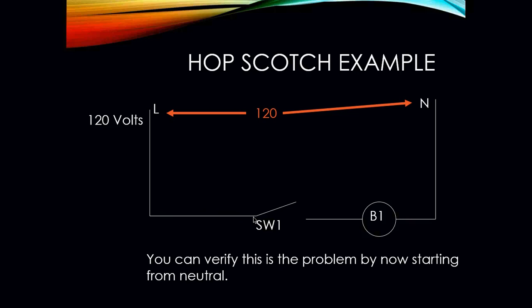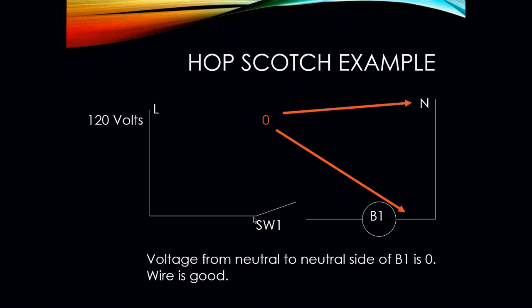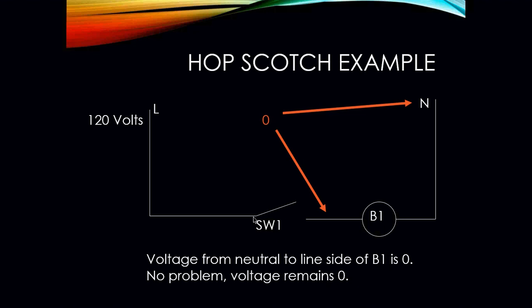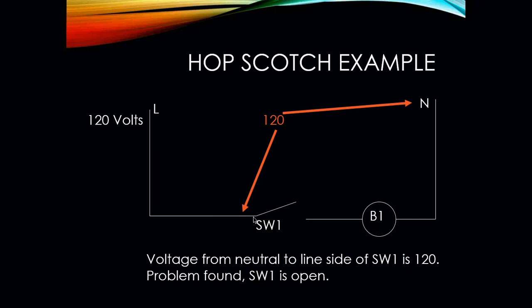To verify that this is the problem, you can now start from the neutral side. You can do it from the other end of the circuit on the neutral side. Again, make sure you have 120 volts across L1 and neutral. You are now going to hopscotch to the neutral side of B1, our load, and we're going to indicate 0. That's telling us that that wire is still good. I go to the line side of my load and I still indicate 0. That's not a problem. Why? Because voltage remains 0. The switch is open. I'm not getting voltage to that side of my circuit. Once I go across my switch to the other side, I'm reading 120 volts. My problem has been found. My switch is open. Once I close that switch, or repair that switch and close it, that bulb or that load should come on.